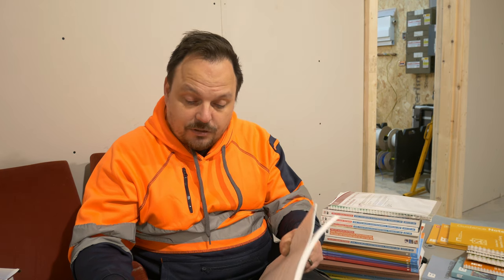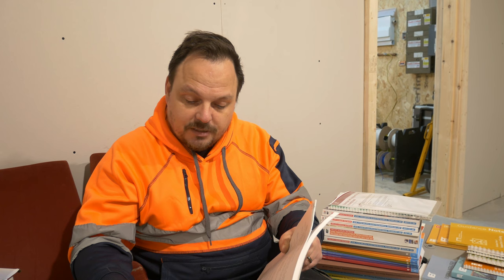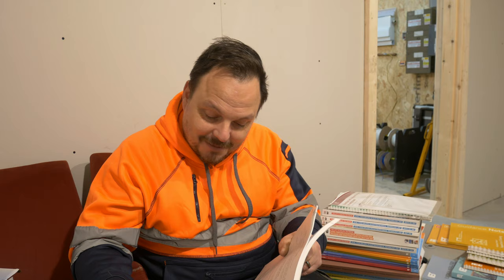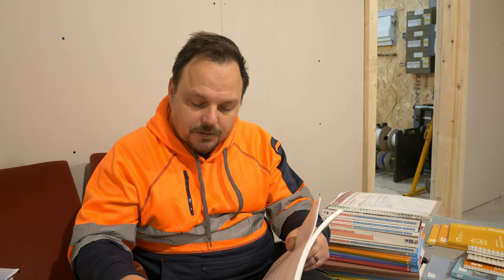So it says here, generally the conductive parts of the metal cable tray or basket system need not be purposely earthed. Some conductive parts of a metal cable support system may be earthed, however, by virtue of fortuitous contact with exposed conductive parts. So that's other wiring systems, or even in terms of an extraneous conductive part, if it is on the steel frame of a building, for example, as well.